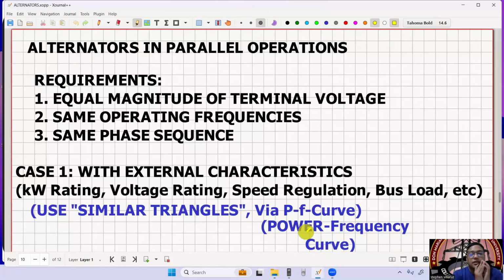But there are things we need to consider when it comes to parallel alternators. These are our requirements. First and foremost, equal magnitude of the terminal voltage, since they're paralleled, the terminal voltage should be the same. Next is same operating frequency, meaning the frequency of the whole system should be definite and the same. Third, same phase sequence, whether it's ABC or ACB, we need to check this carefully.